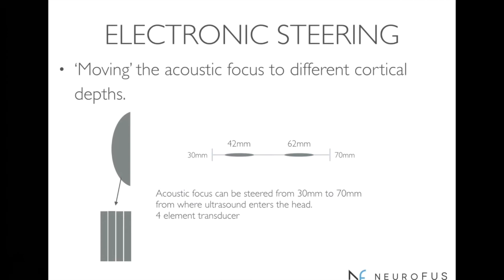But to do that, the ultrasound transducer has actually got four mini transducers in it. Each of those forms a concave dome shape, and they're all stacked on top of each other. Each has been calibrated so you can achieve the same intensity at different depths, even though the power needed to achieve that intensity might differ.